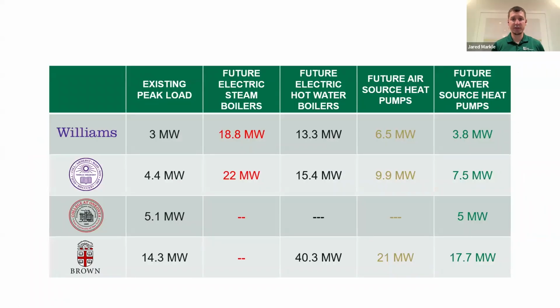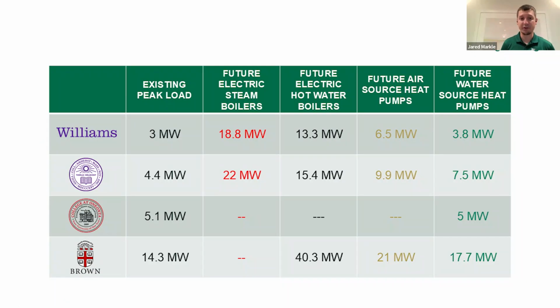Here is what this looks like when you look at real campus loads. These are a bunch of campuses up in the Northeast, including Williams, Brown, and SUNY Oneonta. These are all campuses with relatively low electrical existing peak loads. Williams, for instance, has a 3 megawatt peak load. The addition of electrifying their heating system with air source heat pumps, for instance, adds 6.5 megawatts in addition to their 3 megawatt peak load, so you're at 3 times what their current service is.